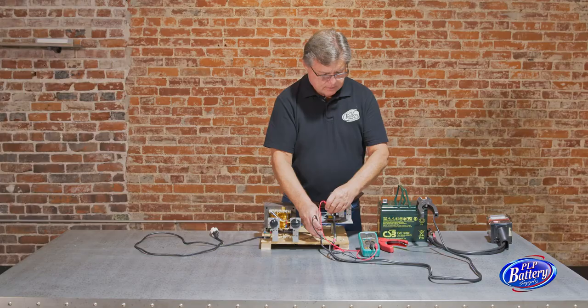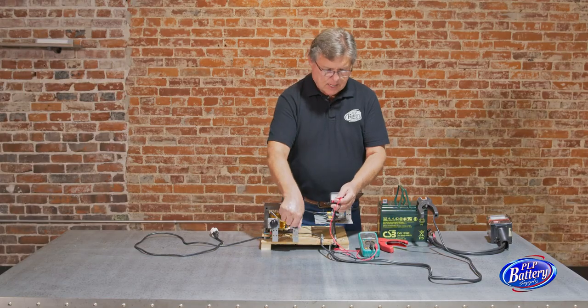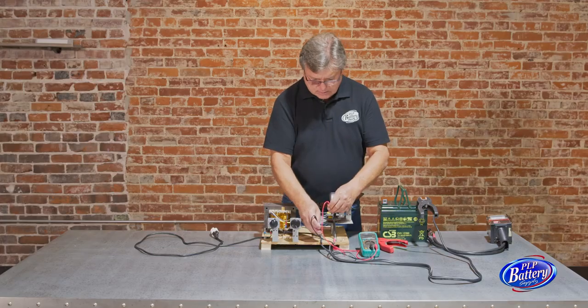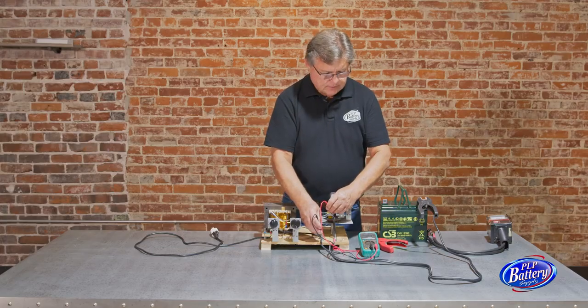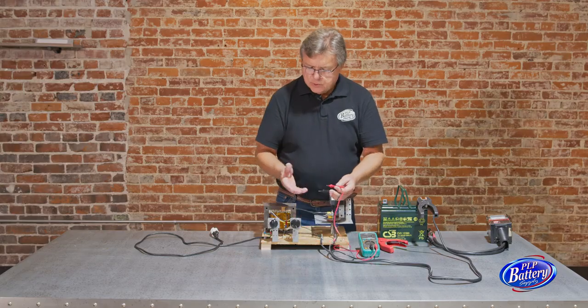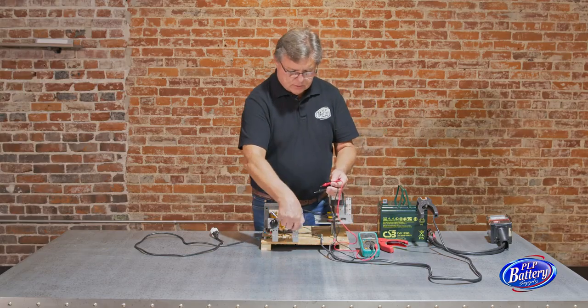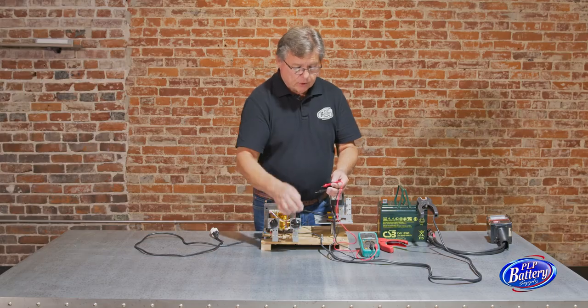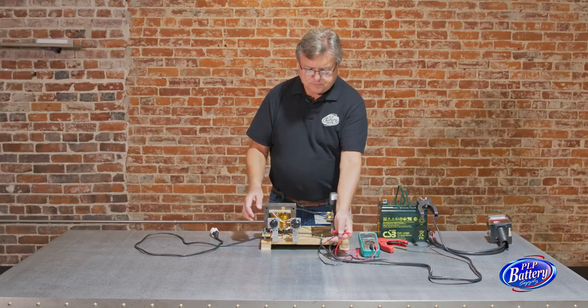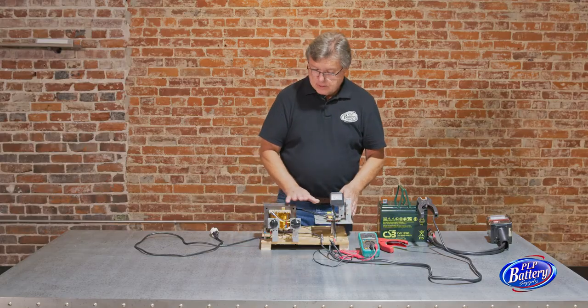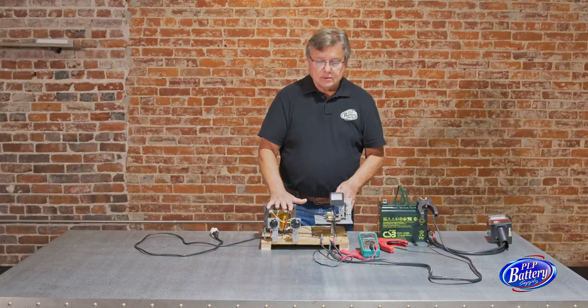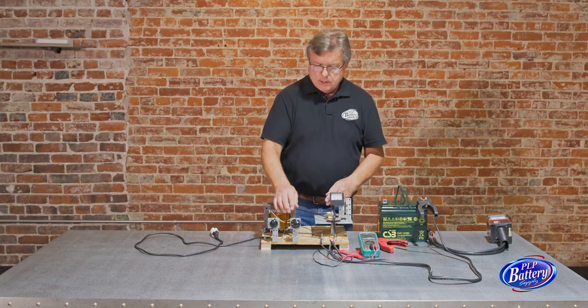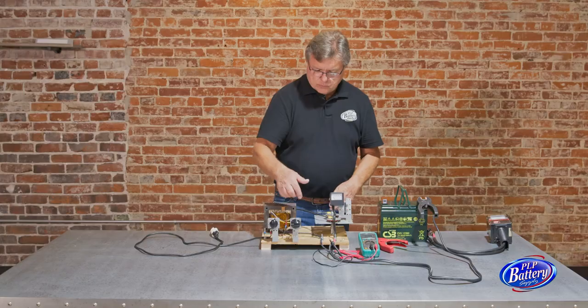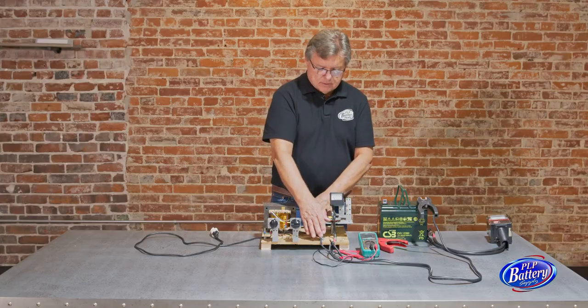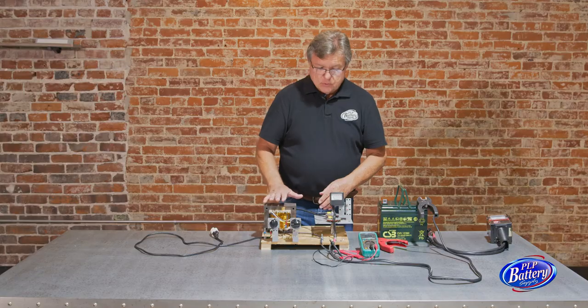Here we are at 14. And on this highest boost setting, it's showing 15, almost 16. So those are not uncommon. Those are pretty typical voltages to test one of these things before you ever hook a battery up to it. That tells us that this thing, the transformer, is good and it's working. So at each one of these settings, we've got good voltage on the AC side on the secondary. That's the first thing that you want to know about your battery charger, is whether the transformer is working.